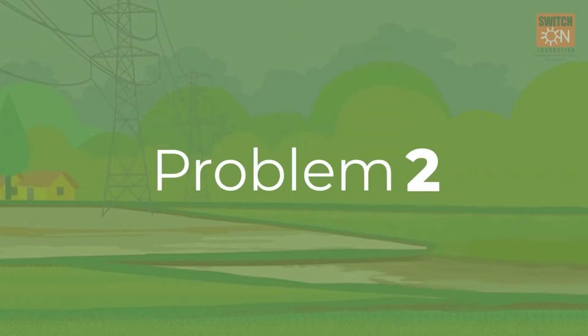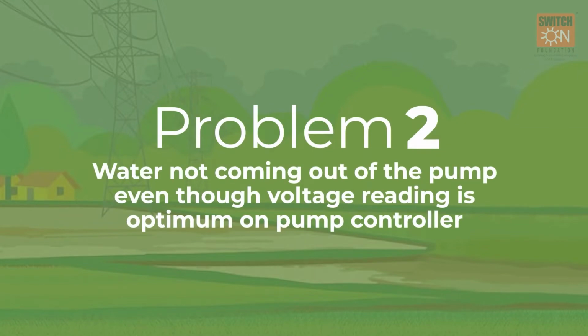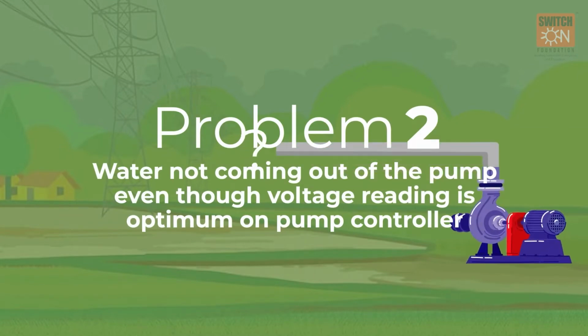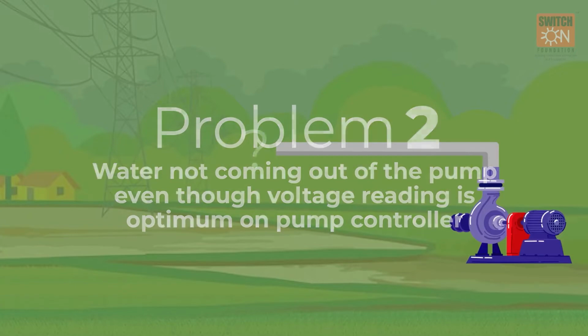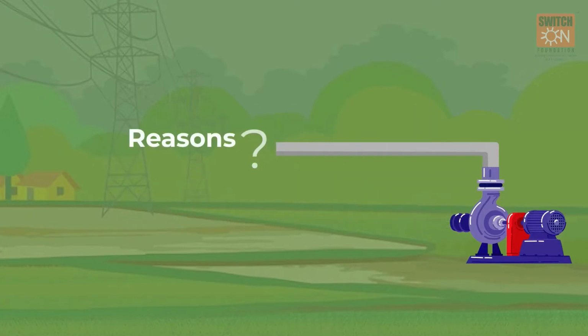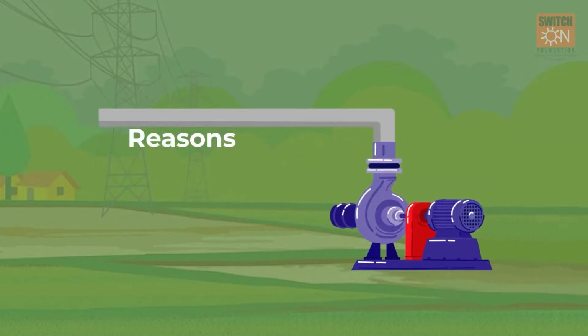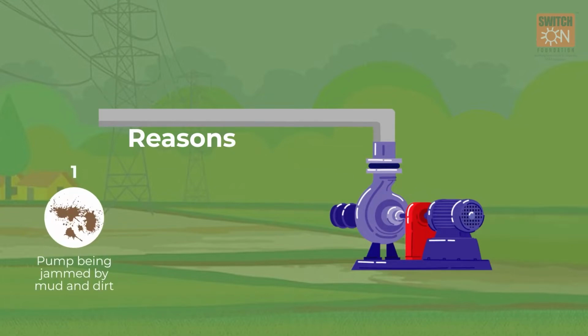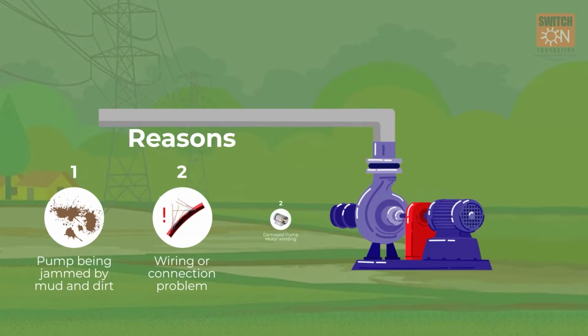Problem 2. Water not coming out of the pump even though voltage reading is optimum on pump controller. Reason: this happens due to inoperative pump, which is caused by various reasons. 1. Pump being jammed by mud and dirt. 2. Wiring or connection problem. 3. Damaged pump motor winding.